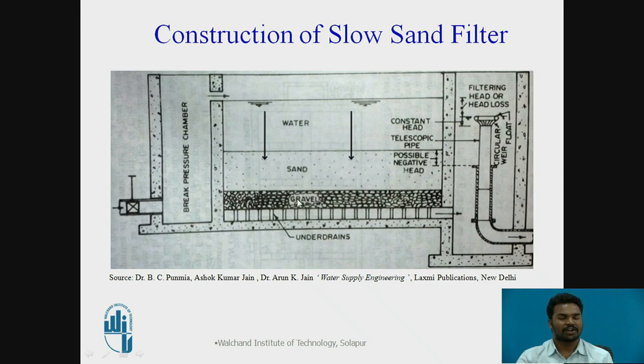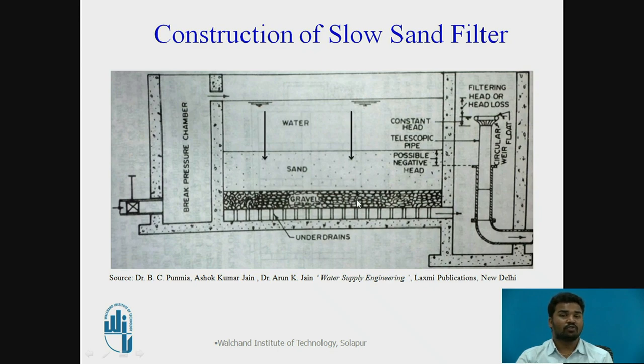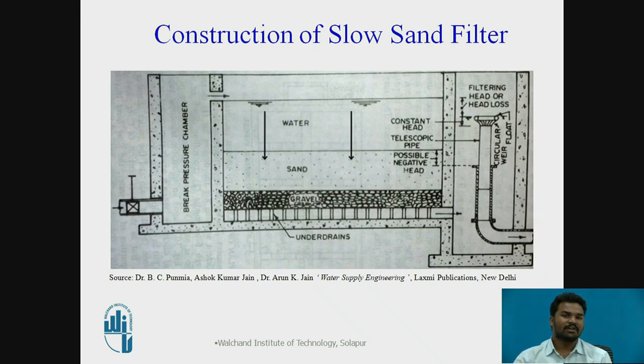The base material supports the sand and uses different sizes of gravel in 3 to 4 layers, with total gravel thickness of 30 to 75 cm. The top first layer has gravel size 3 to 6 mm. The first intermediate layer has gravel size 6 to 20 mm. If four layers are used, the second intermediate layer has gravel size 20 to 40 mm, and the bottommost layer consists of gravels 40 to 70 mm.